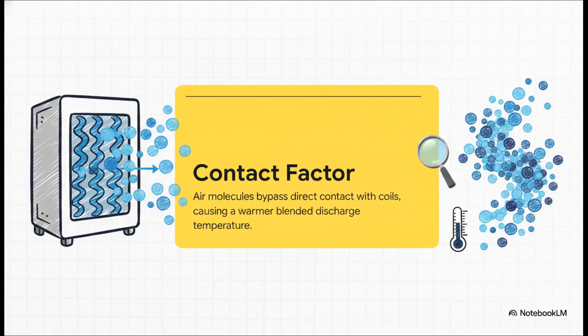And that brings us to the contact factor. Imagine the air rushing through your air handler like a massive, chaotic crowd trying to squeeze down a narrow hallway. Not every single air molecule is going to bump into the walls, or in this case, those freezing metal coil fins. The air that bypasses direct contact just doesn't get as cold. It simply mixes with the air that did touch the coil, resulting in a final, blended discharge temperature that is quite a bit warmer than the coil itself. And that right there is exactly why you get a 16-degree vent breeze from a 6-degree coil.